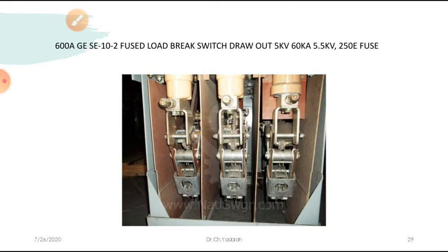Some chutes are provided. That means whatever arc is produced during opening and closing, the arc enters different cells, different portions. Once the solid arc is split into the different chutes, which are made of metallic parts, the heat present in the arc is automatically absorbed by the chutes.